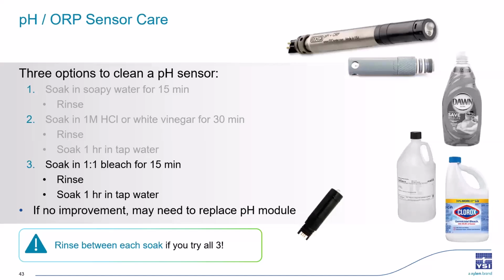If these cleaning steps don't work, you might have to replace the pH sensor or the module, but plan to do that after you take it back out of storage. Since the pH bulbs do have a usable life of about a year, whether they're being used or not, you can go ahead and wait to do that when you take it out of storage.